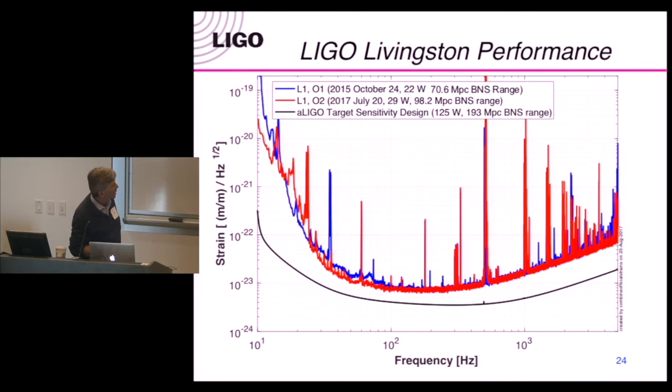There are calibration lines put in here. I think, which one? This is a calibration line. There are a few others. I think that's a calibration line up there that allow us to actually calibrate the instrument. And then some of these lines, this guy and this guy, are actually basically violin modes.